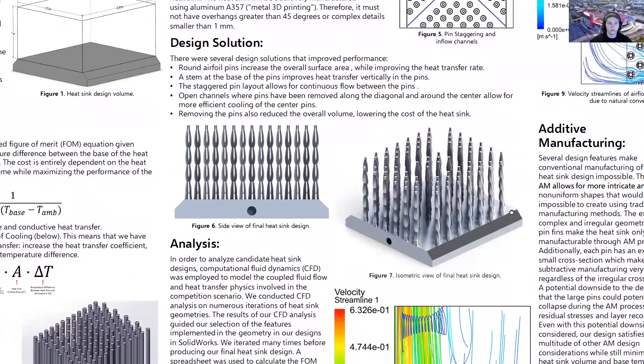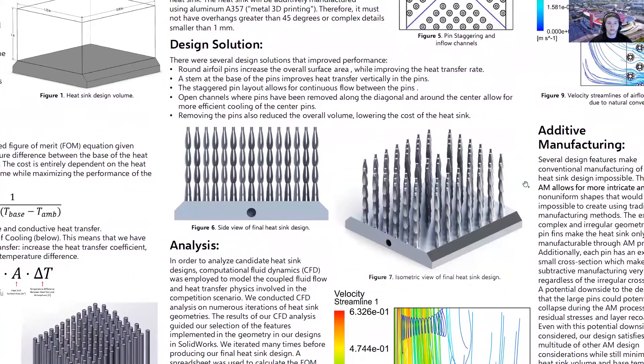Our final design was based off many design principles previously outlined. We went through multiple design iterations with the intent to improve the previous iteration. Some key iterations that we implemented were round airfoil pins, a stem at the base of the pins, staggering of the pins, as well as implementing air channels within the heatsink. These combined modifications allowed for improved performance and reduced the overall volume of the heatsink.